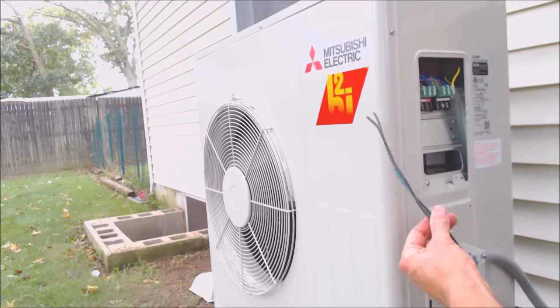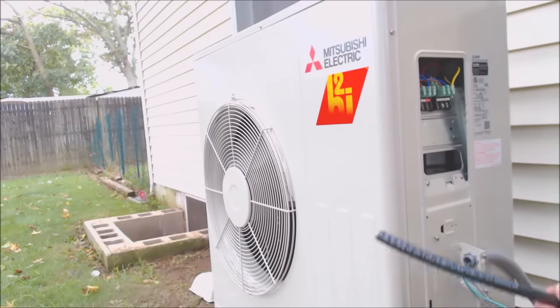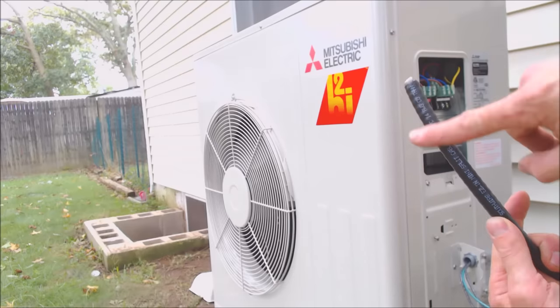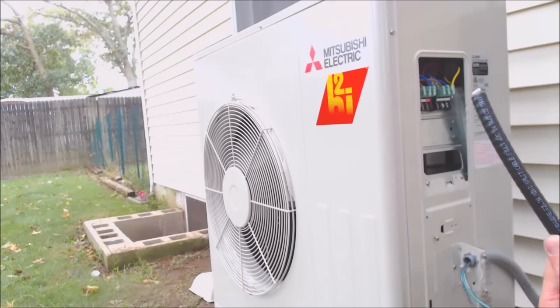Hey guys, this is AC Service Tech and today we're looking at how to wire in a Mitsubishi mini split heat pump unit. This is a single zone unit and we have our whip from our disconnect with our three THHN wires. We're going to be using our Southwire EZIN, which is going to be our power wire to the indoor unit and our communication cable for the indoor unit.